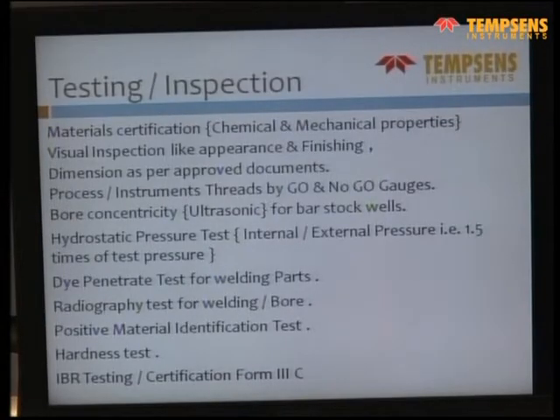Various kinds of testing and inspection are carried out on the sensors. Some of them are being listed here. This is on the thermowells. One is material certification, which would be chemical and mechanical. Then visual inspection, like appearance, finish, and dimension as per approved drawing. Then threads as per the gauges, and bore concentricity, which can be checked by ultrasonic or by physical measurement. Then hydrostatic pressure, mostly external.